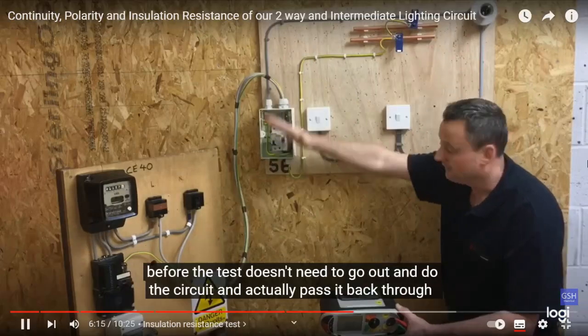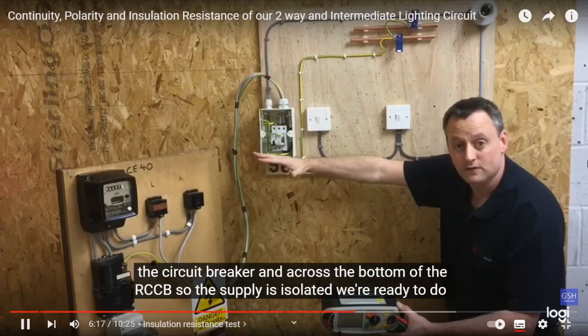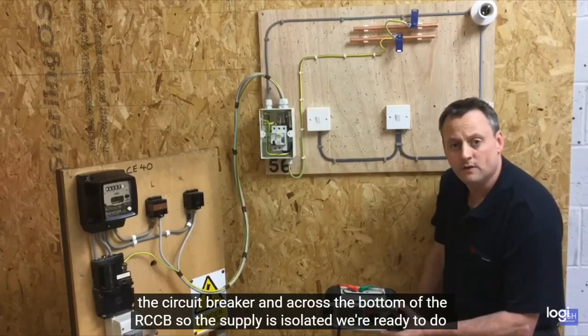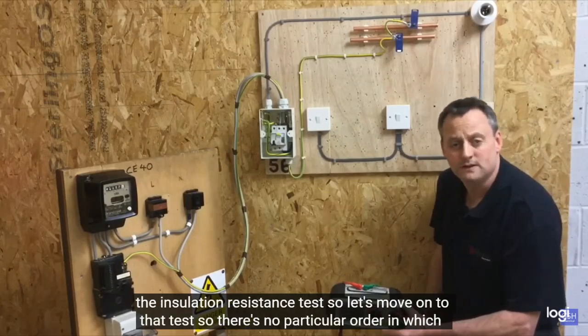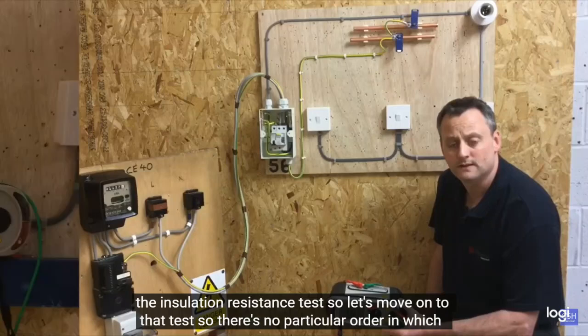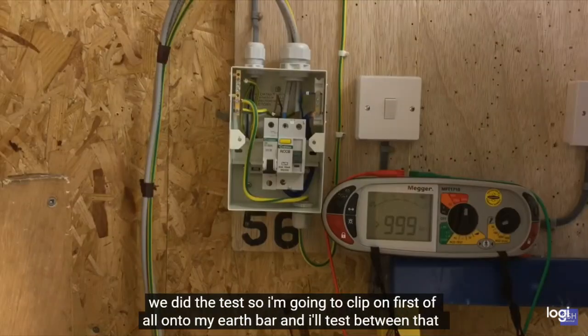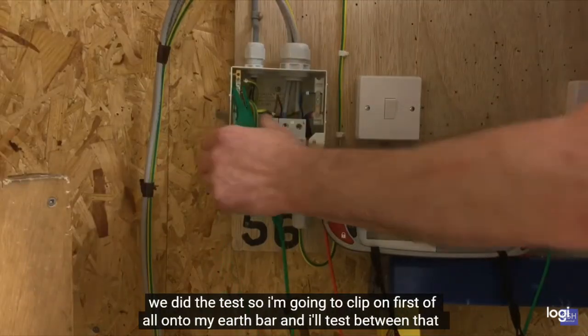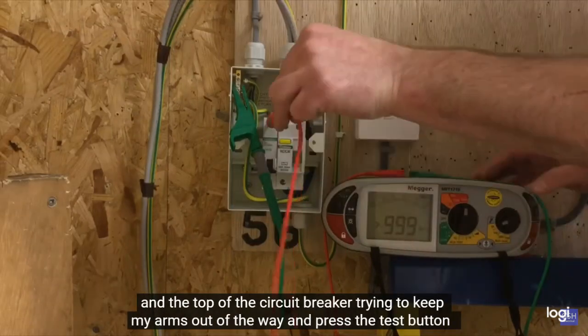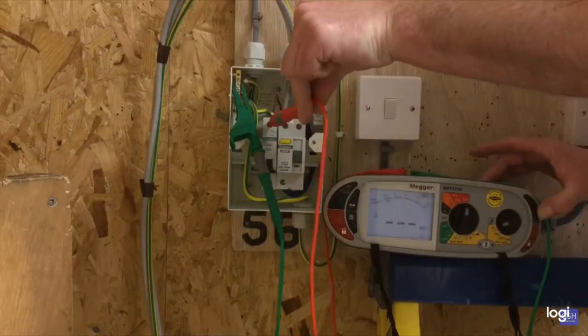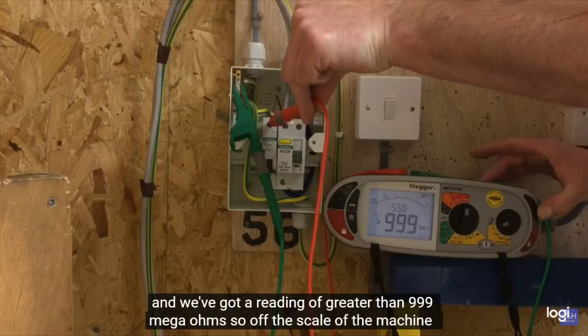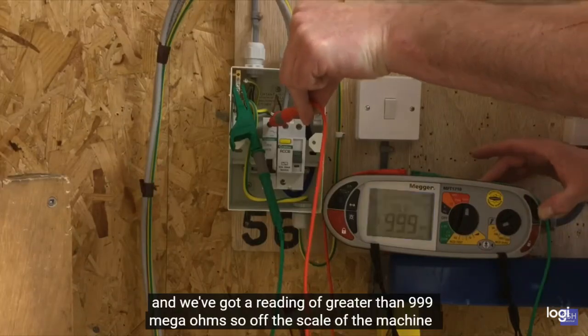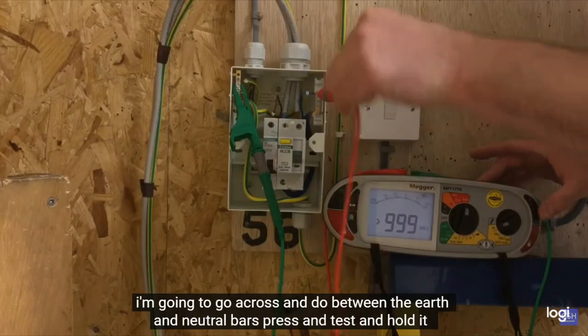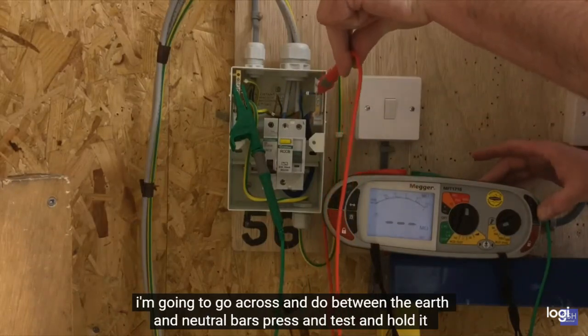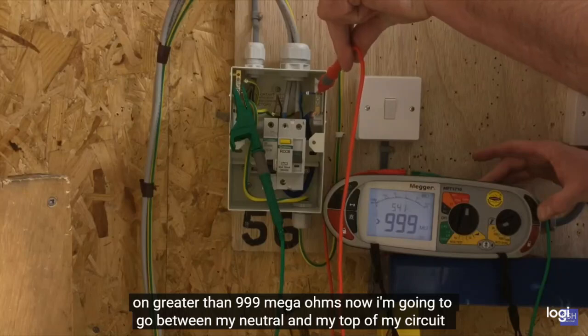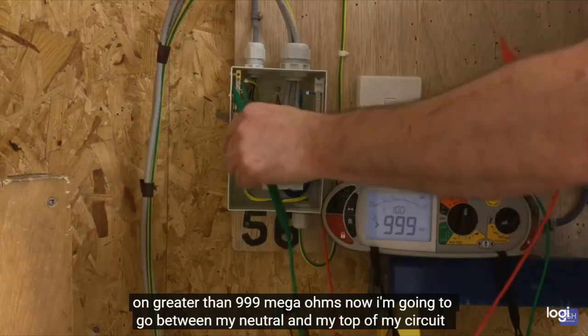There's no particular order in which we do the test, so I'm going to clip first of all onto my earth bar. I'm going to test between that and the top of the circuit breaker, trying to get my arms out of the way, and press the test button. Got a reading of greater than 999 megohms, so off the scale of the machine. We go across and move between the earth and neutral bars. Press and test, hold it on. Greater than 999 megohms. Now I'm going to go between my neutral and the top of my circuit breaker for the line, so neutral and line. Once again, I've got a reading greater than 999 megohms.